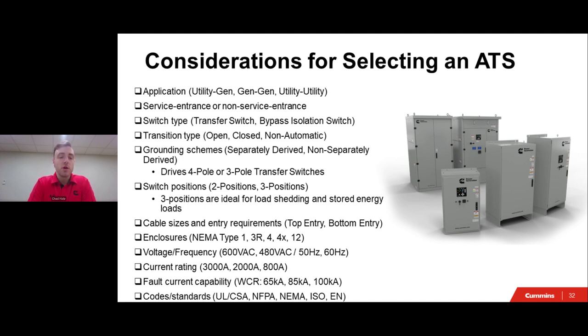And in the case of the enclosure, do you need to take into consideration the environmental factors of where your transfer switch is being placed? If indoors, is a Type 1 or Type 12 needed? Are you in a salty environment? If so, maybe you need to look into a NEMA Type 3R or a 4 style enclosure. And then lastly, making sure you're looking at the one line to make sure you're specifying the right voltage and hertz for your application, and making sure you have all the right ratings and are up to code when it comes to the laws and regulations that govern your transfer switch operation.